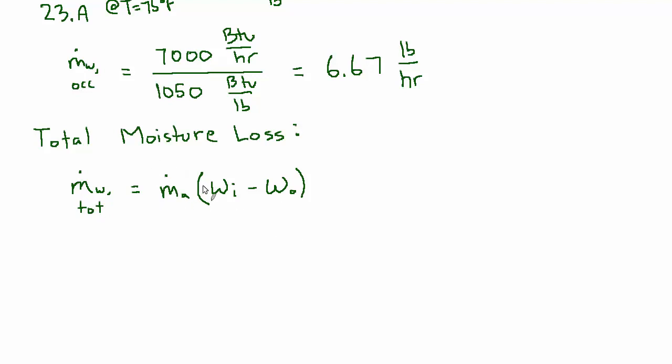There's a little trouble with this in that the mass flow rate of air is actually different for the two streams. We know the volume is the same, right? The volume out and the volume in have to be equal. And in general we're satisfied to divide the volume flow rate by the specific volume, which will give us the mass flow rate. And then this number is in CFM so we'll also have to multiply by 60 minutes per hour because we want to do this on a per hour basis.